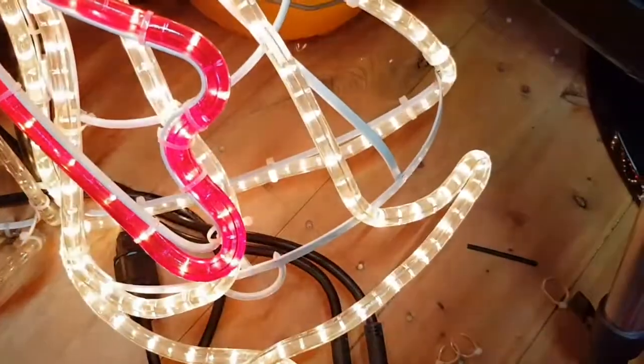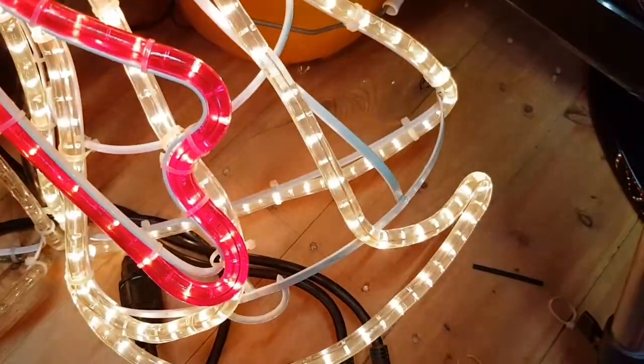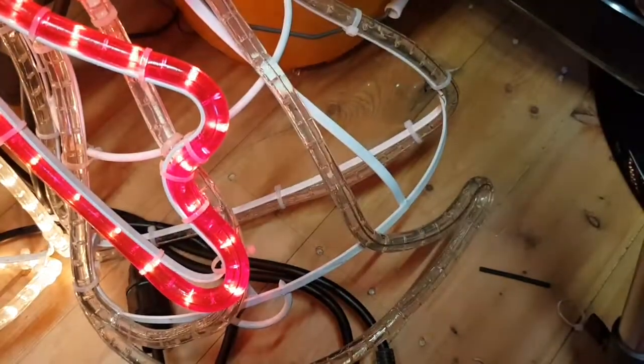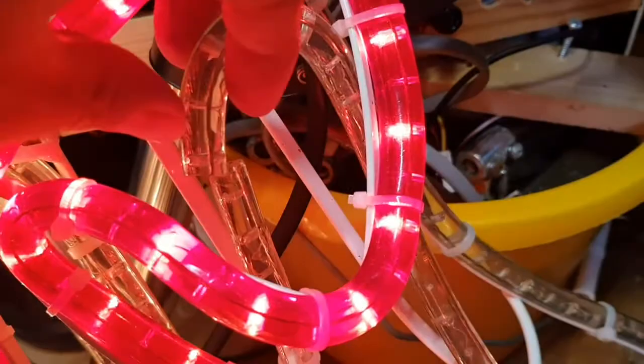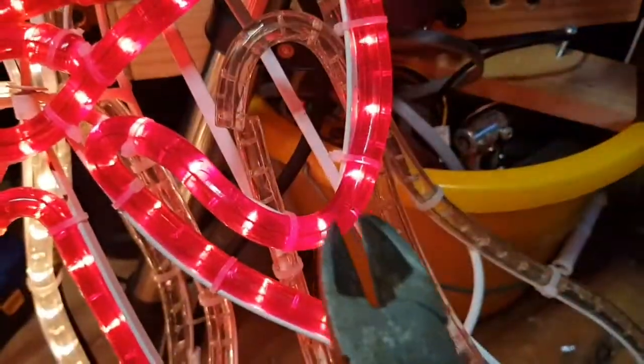Okay, I'll have a think. I could replace it anyway. It's gonna have to be replaced, I can't fix it, can't get in there and solder it or anything. Okay well we'll cut it out still. So obviously with the power off, you just slice it through with a big pair of cutters at the actual break point. And if I squeeze it again you'll see that's the section that's out. So now I've got to cut it there. So big cutters and turn the power off first.